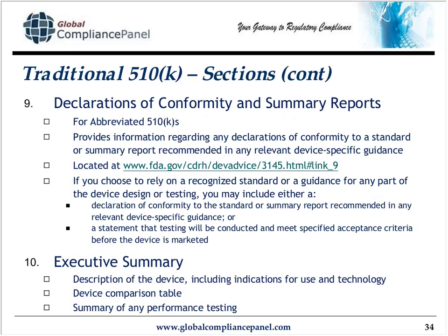If you want to rely on a recognized standard or guidance, you can include either a declaration of conformity or a statement that testing will be conducted in the future and it will meet specified acceptance criteria.